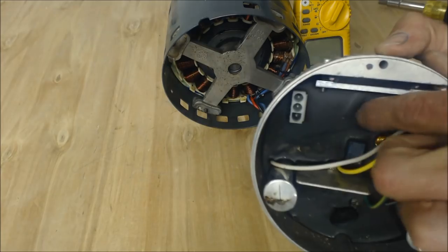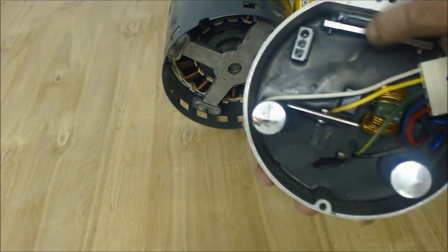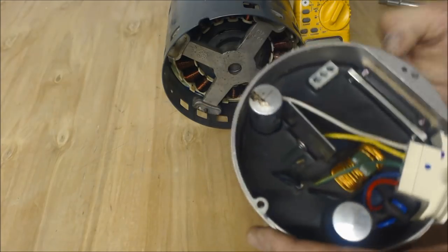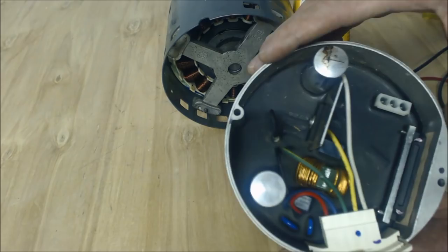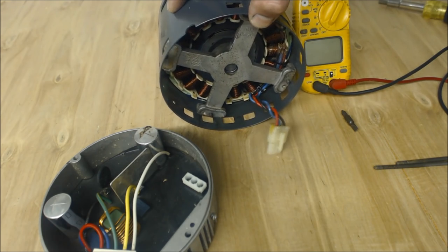This board is what's called fully potted — it's actually resistant to water instead of just having an open control board. You can see the part that actually failed on this. Basically this is a control board that's encased. We're going to set this to the side, and here you have your wound motor.